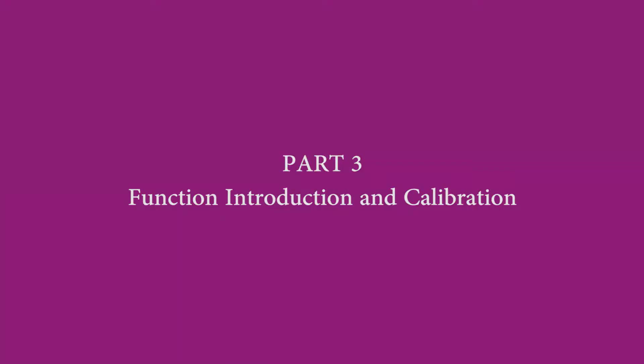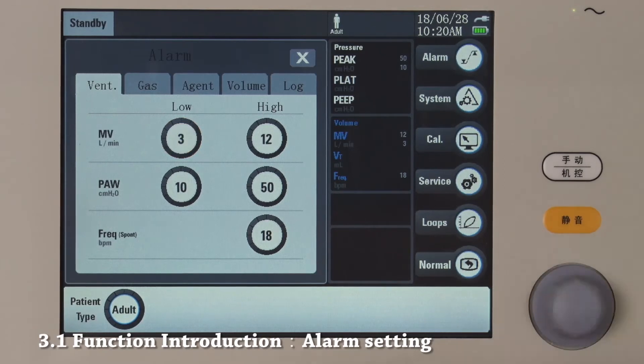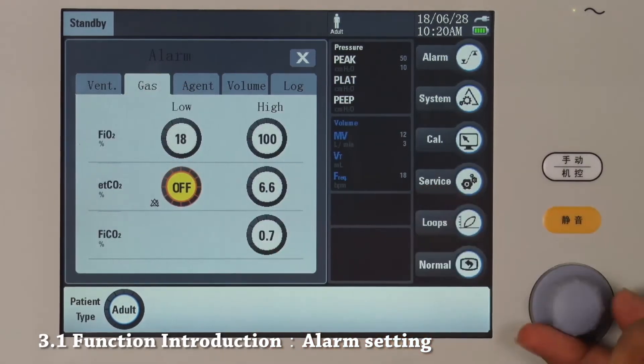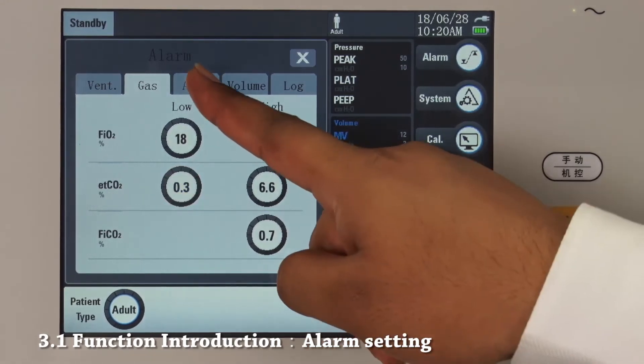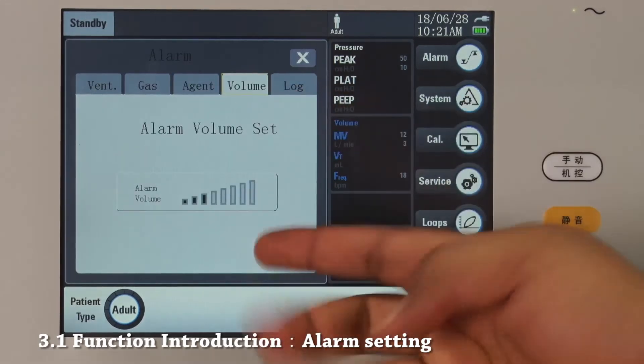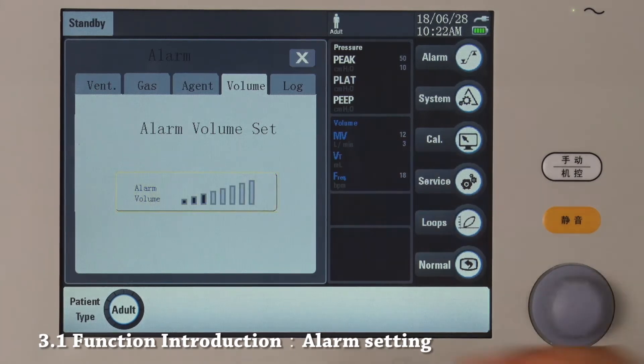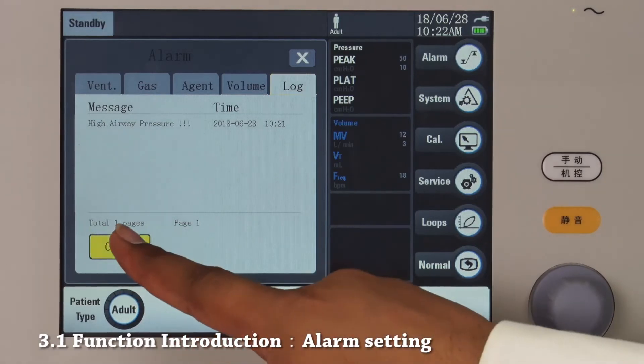Part 3: Function introduction and calibration. This is our alarm option. In the settings, we can change alarms for ventilation parameters, for gas parameters, and also for agent parameters. Apart from that, we can change the alarm sound volume, and in the log part we can log all the alarms that occur during the time. Press clear in order to clear the log.